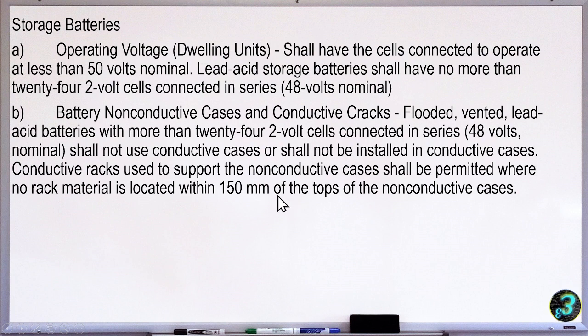This means that your battery, 150 mm from either side, especially on the top, should have no conductive material in its perimeter. So that is what this standard means, that is from the casing, from the rack itself.